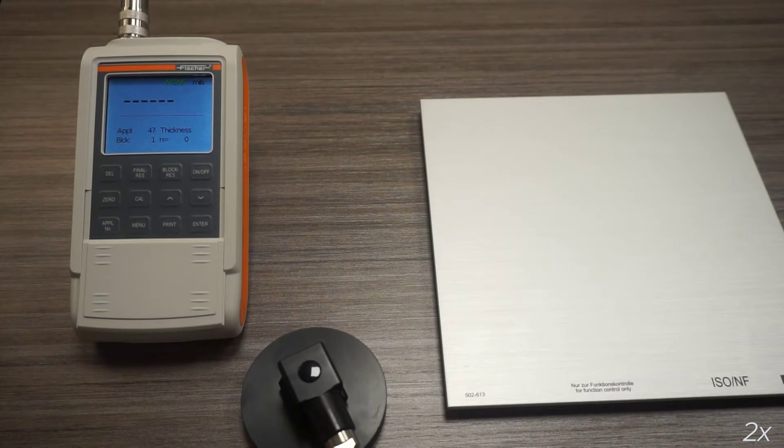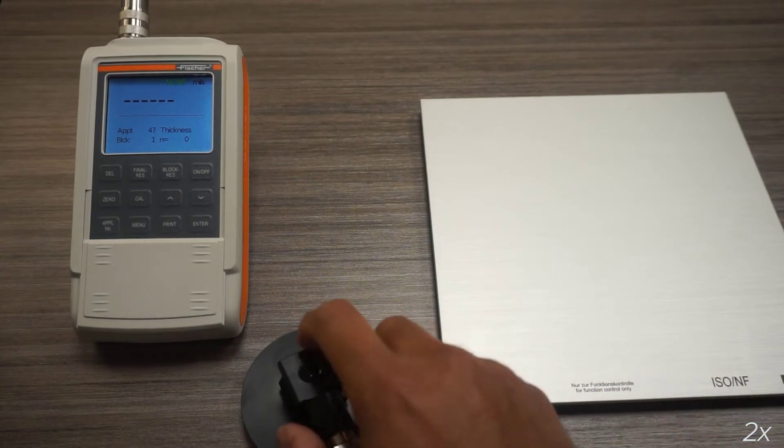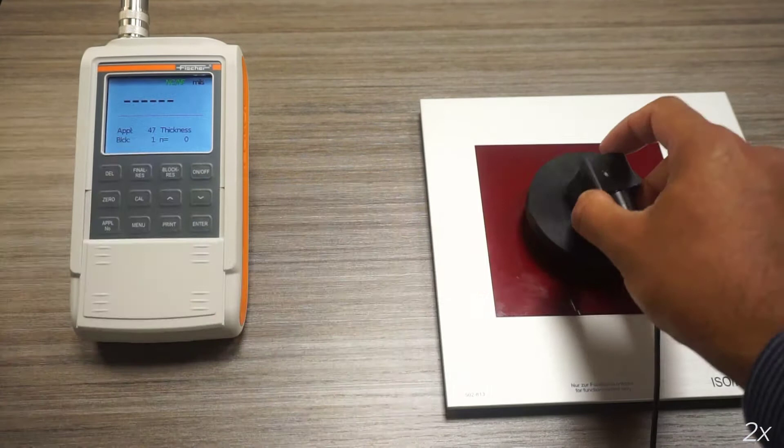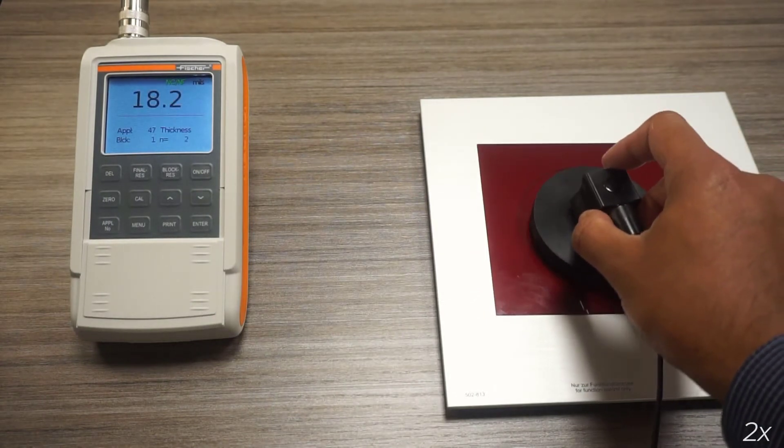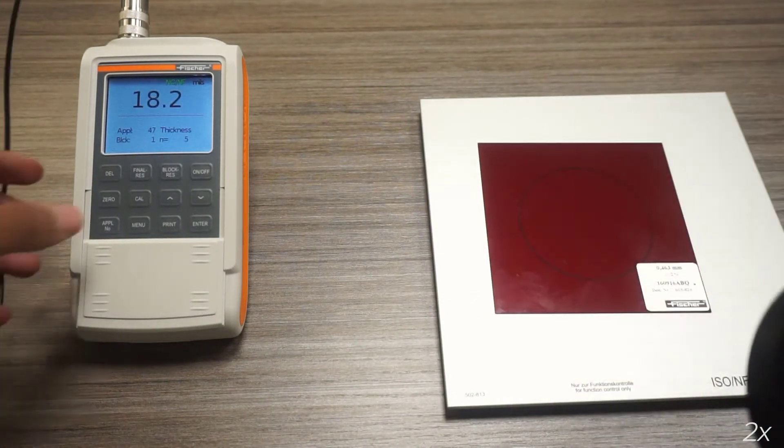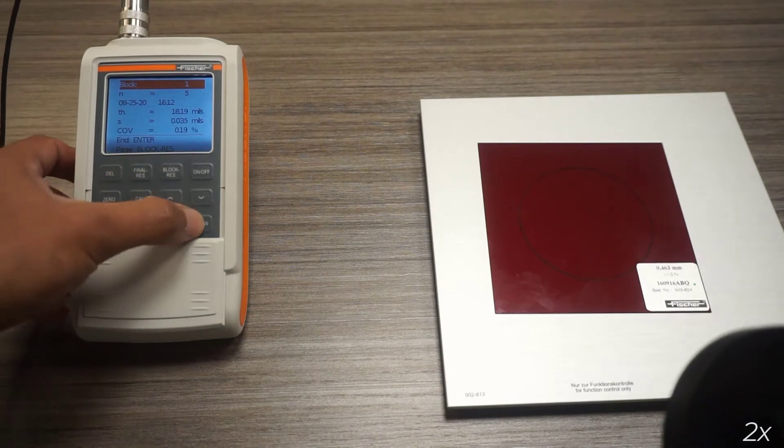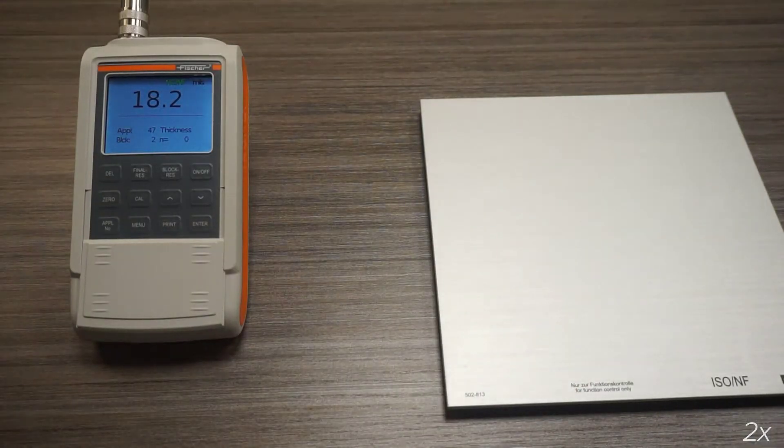This instrument has already been calibrated, so I'm going to do a quick check on these standards to ensure that it's performing properly. This is not something you have to do every time you want to take a measurement, but it does show how accurate and precise the instrument is on uniform materials.